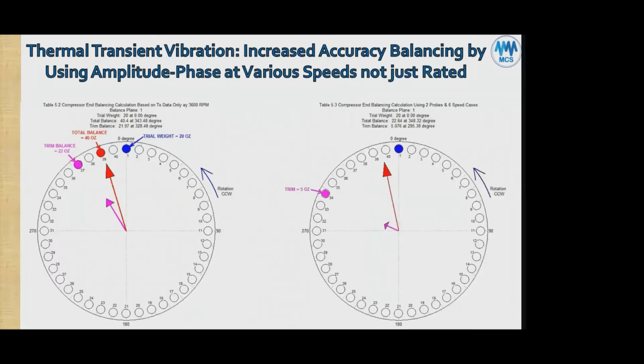And the final slide we have is an example of, again, another gas turbine driven compression train, or sorry, gas turbine driven steam turbine generation unit, all on one shaft. Here I just captured this as a nice example where the author recommended, when you're judging the thermal transient vibration unbalance, plus you have the fixed unbalance of the rotor, the cold unbalance of the rotor, and you're trying to resolve both.